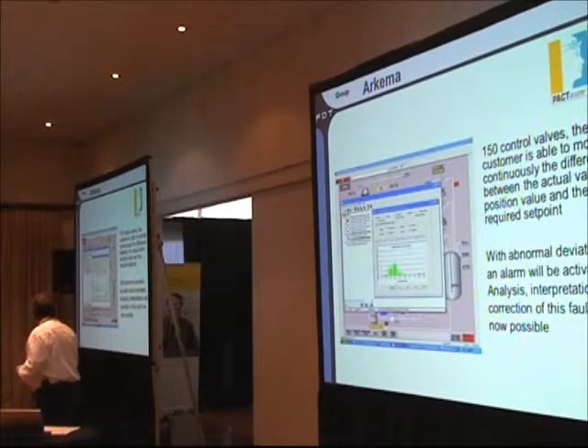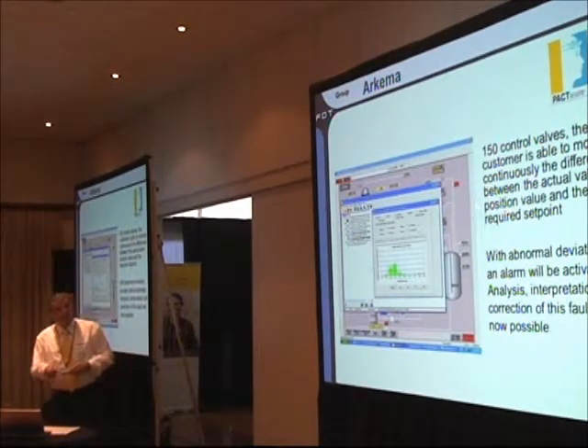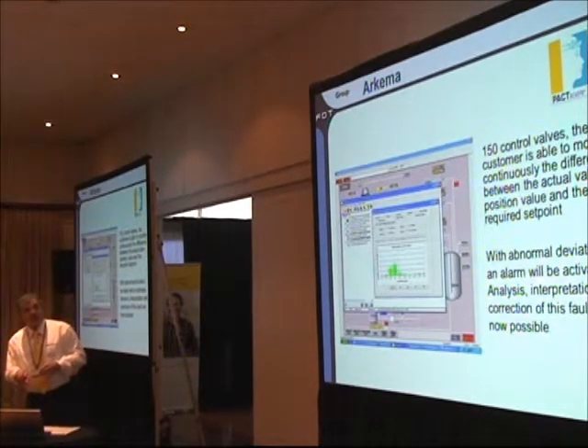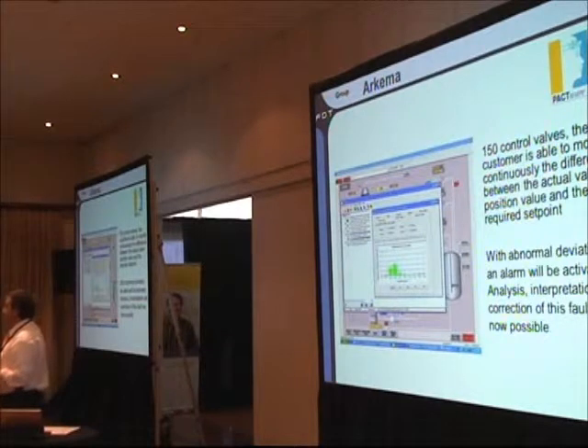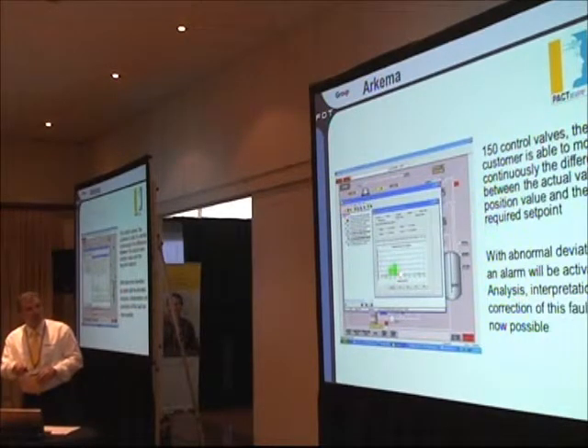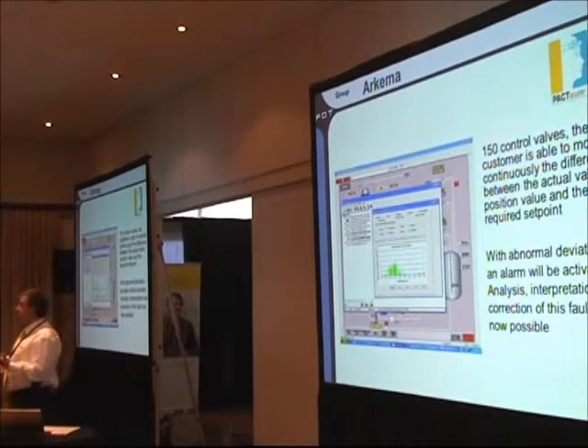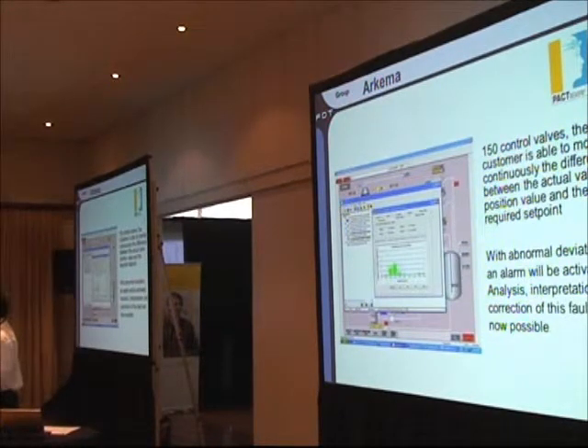This is a big performance improvement, and the DTM itself could give alerts if there was an abnormal deviation - alarms were activated. It all comes from the DTM. You can program it so that if my valve is at its optimum and then moves in one direction or another, I can set alarms that get activated.